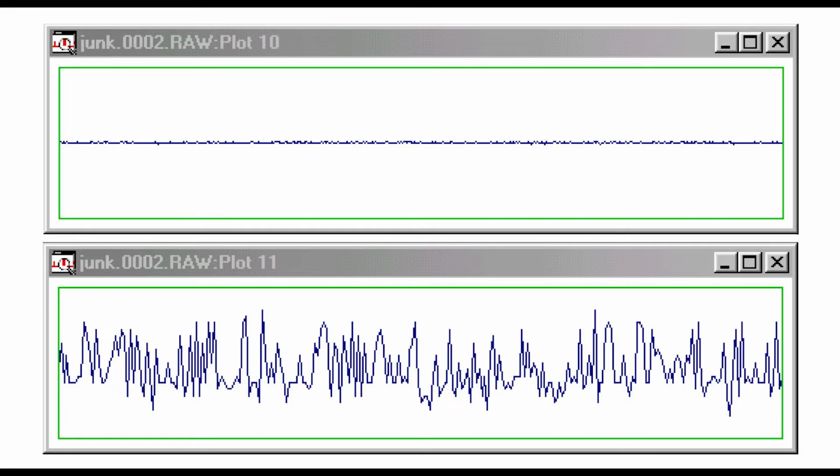As mentioned above, most detectors produce flicker noise on the order of several microvolts, and this is usually greater than the step size. Therefore, noise, and not resolution, is frequently what determines the height of the smallest peak that can be detected. In the presence of noise, increasing the resolution of the digital-to-analog converter simply provides a better measurement of the noise. Only when the detector is particularly quiet will increasing the resolution of the digital-to-analog converter improve the detection limit.